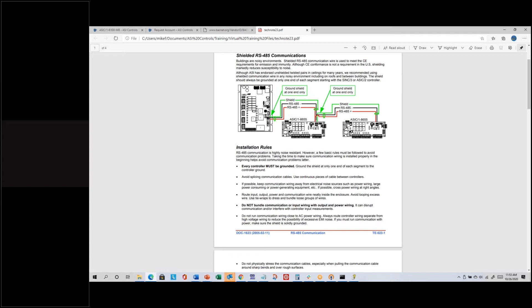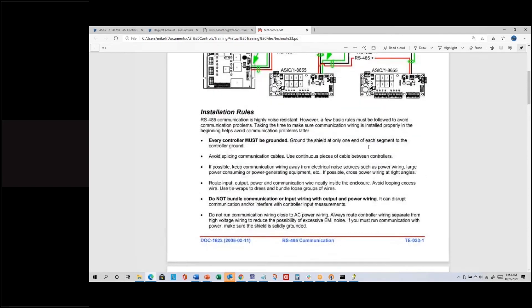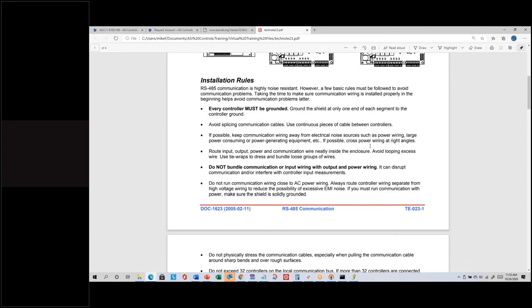I would never recommend going back to re-terminate shields on a network that's communicating well, but for new projects there are advantages to terminating the shield this way. The red and black wires shown indicate that we are polarity sensitive — all the minuses need to go together as the black wire, and all the positives need to go together as the red wire.